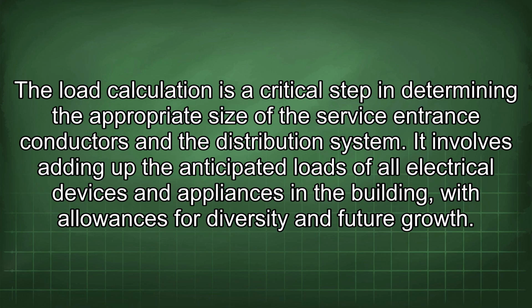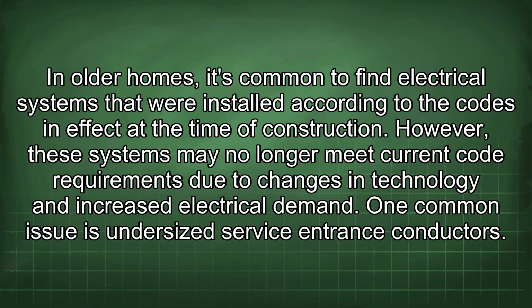The load calculation is a critical step in determining the appropriate size of the service entrance conductors and the distribution system. It involves adding up the anticipated loads of all electrical devices and appliances in the building, with allowances for diversity and future growth. In older homes, it's common to find electrical systems that were installed according to the codes in effect at the time of construction. However, these systems may no longer meet current code requirements due to changes in technology and increased electrical demand. One common issue is undersized service entrance conductors.